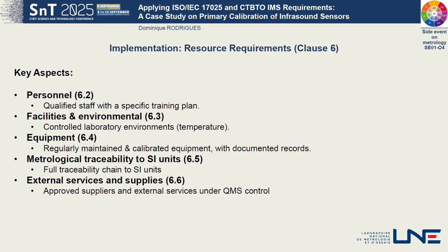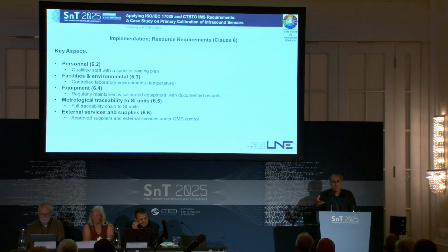Okay, so the next block for resource requirements. So here there are 5 items. For the personnel, of course, we need a competent staff. So for the specific new calibration service, the operator is usually trained by a first companion phase. This companion phase can be shorter or longer depending on the profile of the operator. And anyway, at the end, the qualification is formalized, of course, and based on objective criteria. So usually it's a comparison against an operator who is already qualified.